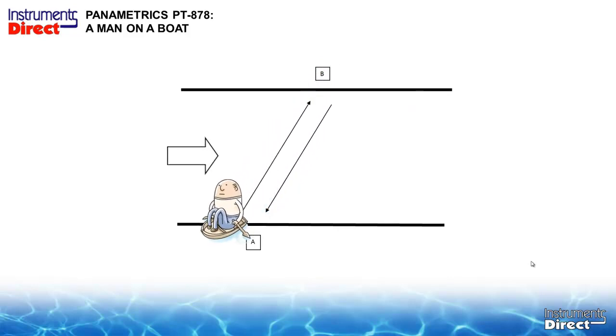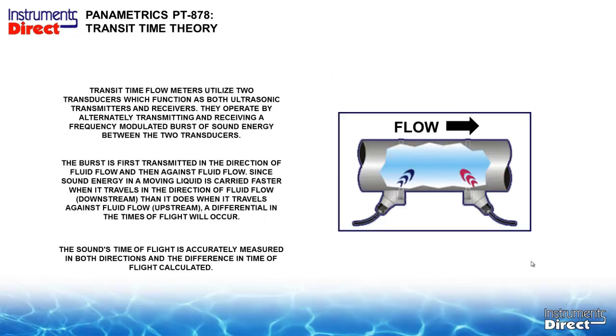And that differential of that transit time is how we calculate how fast the river is flowing. And in this case, how fast the flow is flowing inside a pipe. We have a bird's eye view here of this pipe, and the same analogy is, as opposed to going across the river here, we're going to ricochet it off this back wall. So we're looking down from the top. The sensor on the left will send a sound burst across the pipe, ricochet off the back wall, come downstream. We're going to measure how long it took to do that.